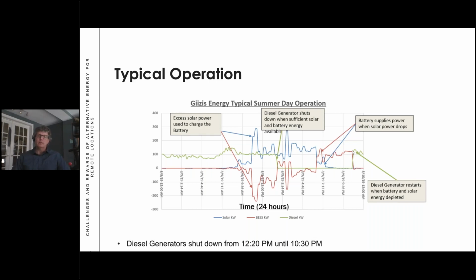We get to this point, and the state of charge of the battery is about 25%, and we send a signal back to the diesels to start back up and take over powering the community. Again, 25% was chosen to give the diesels enough time to start up without risking an outage. We don't want the battery to go to zero with the diesel not started and the community left with no power, so this gives ample time for the diesel generators to start back up and take over.